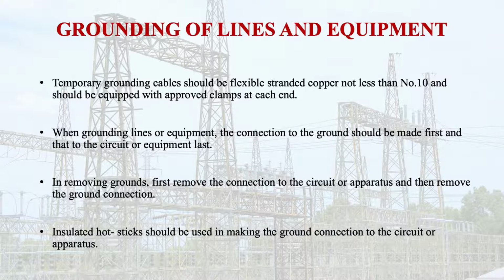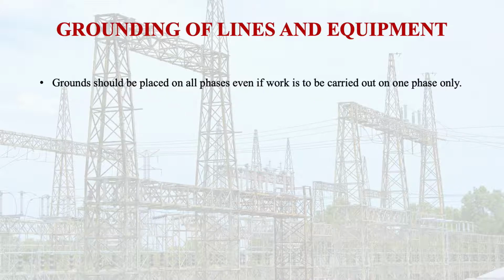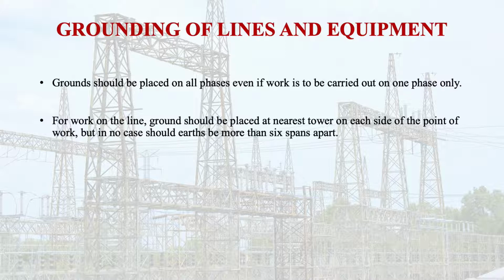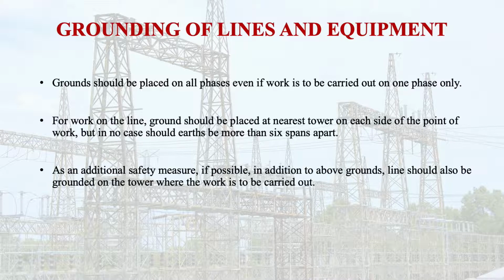Now learners, insulated hot sticks should be used in making the ground connections to the circuit or apparatus. So remember, the ground should be placed in all phases, even if work is to be carried out on one phase only. So for work on the line, ground should be placed at the nearest tower on each side of the point of work, but in no case should earths be made more than 6 spans apart. As an additional safety measure, if possible, in addition to the above grounds, the line should also be grounded on the tower where the work is to be carried out.